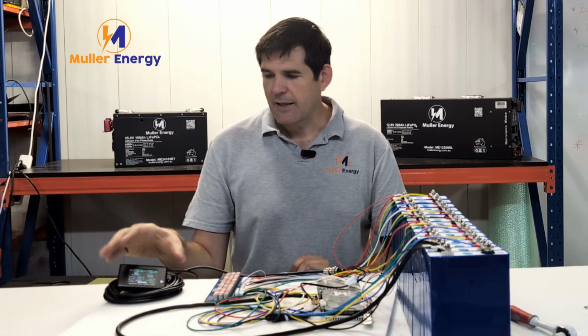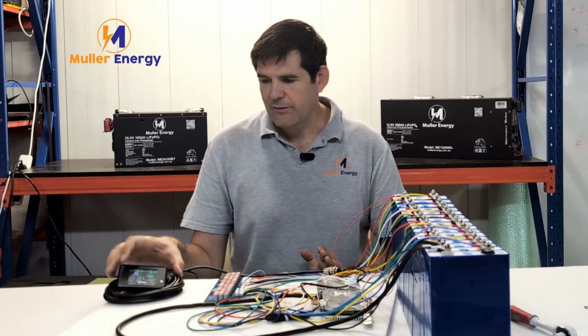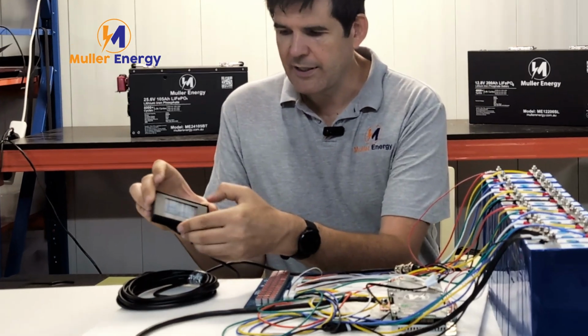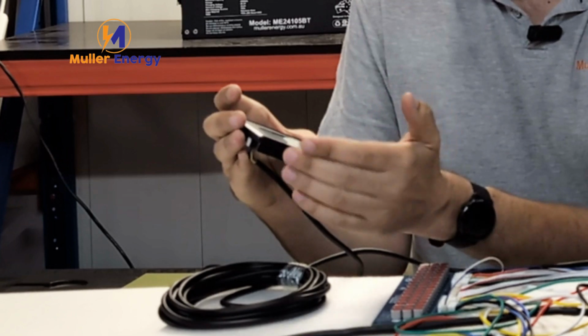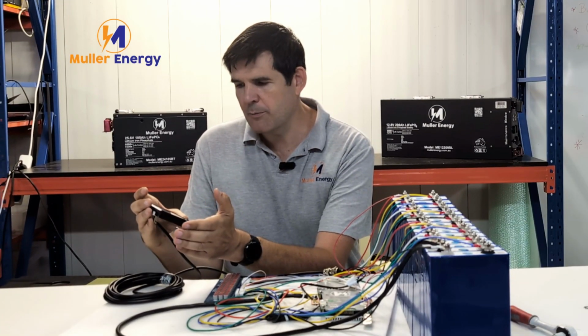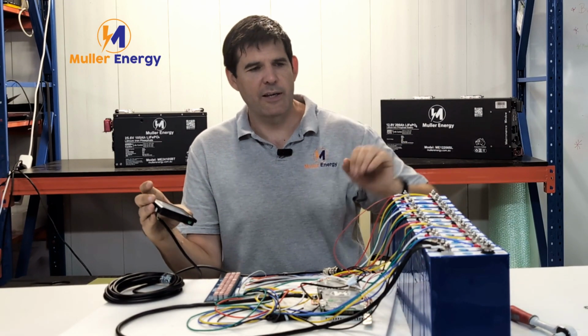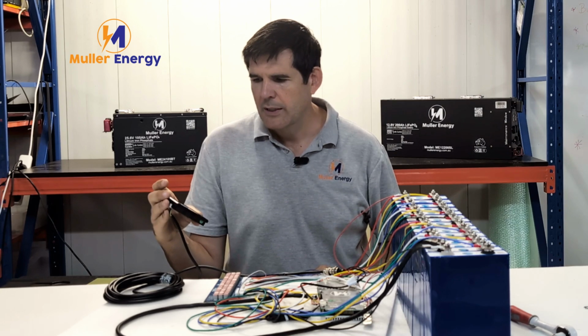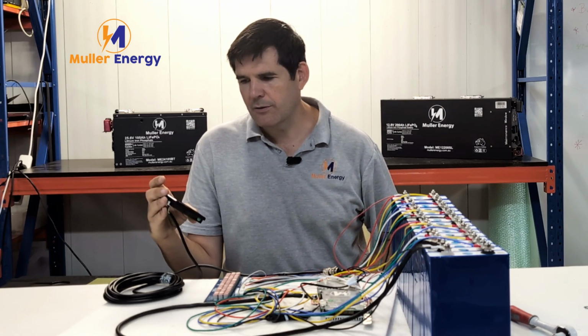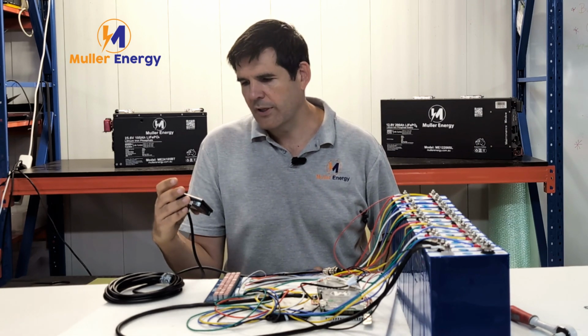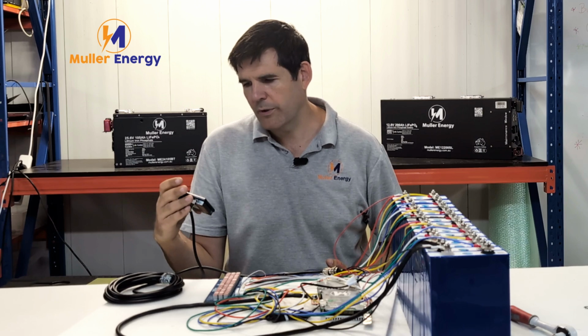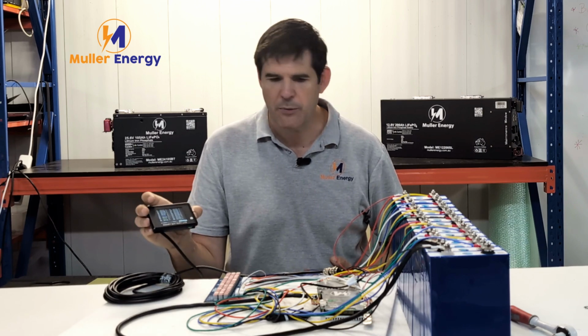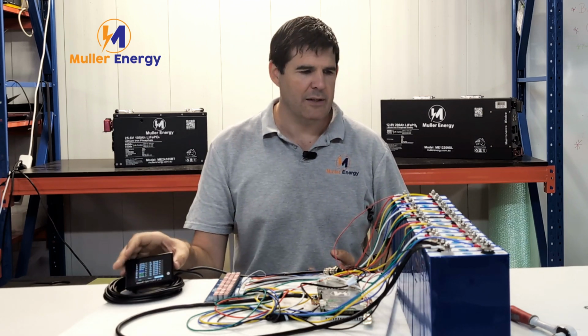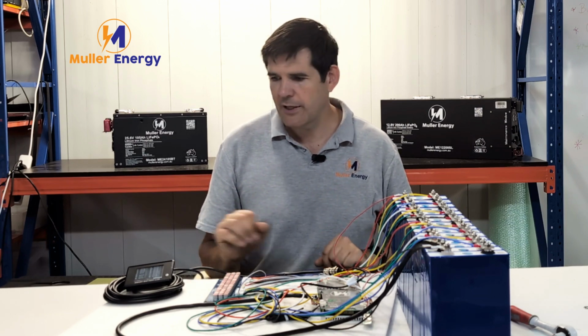That's the main settings here. On screen 3, you can see all the cell voltages. This one isn't in balance just because it's a bit of a prototype setup, but normally you'd want it in balance. Here it's not horrible, we've got 16 millivolts difference, but normally you'd want it to be 5 or less.